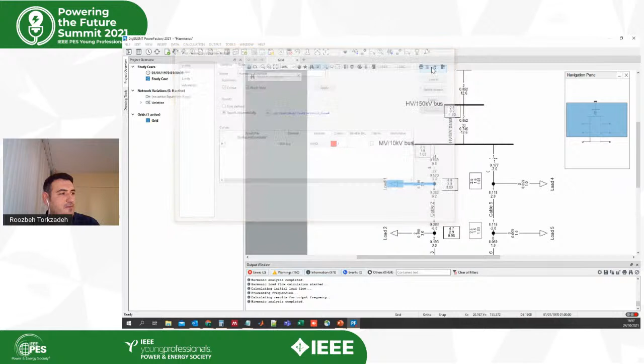So you can, for example, focus here and then press this one. So for the fifth harmonic, the harmonic distortion is about, let me also make it a little bigger, it's 1.6, and for the seventh harmonic, it's 1.5. And also for the 11th and 13th harmonic, you can see the values. So this is one of the objectives of doing power quality analysis with PowerFactory.